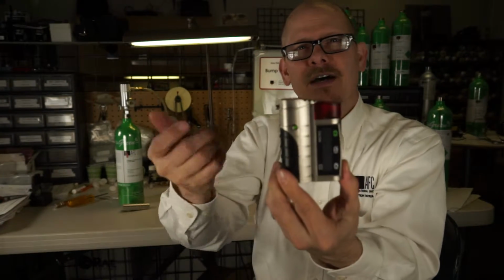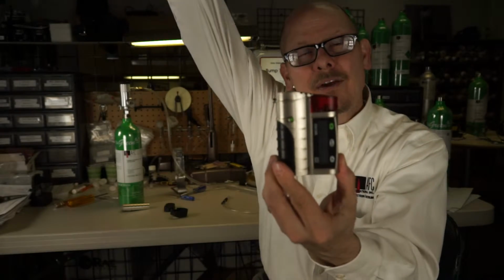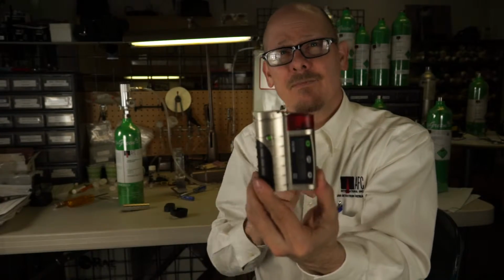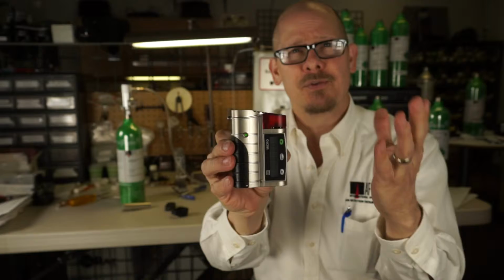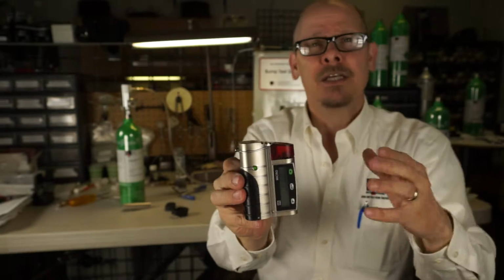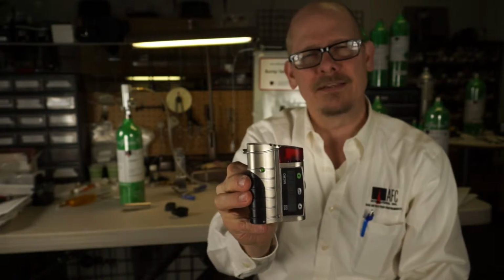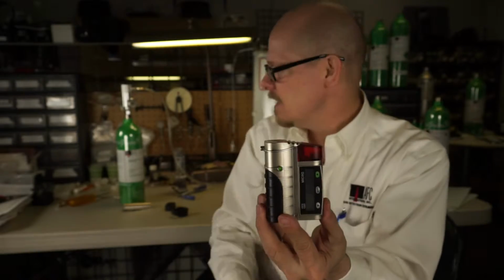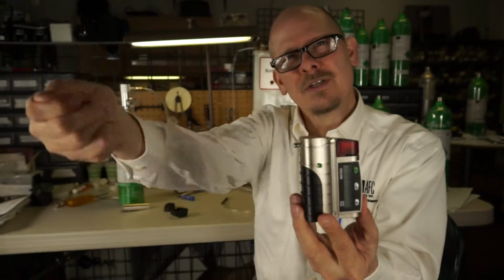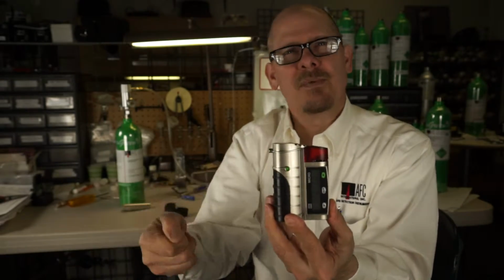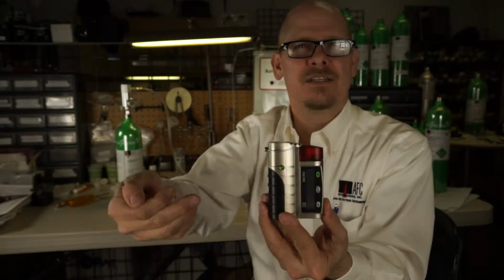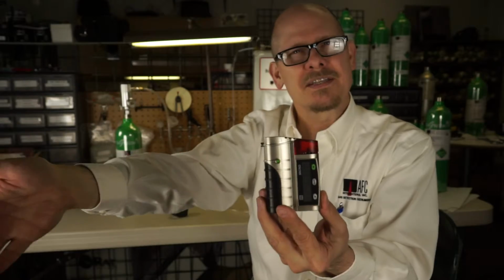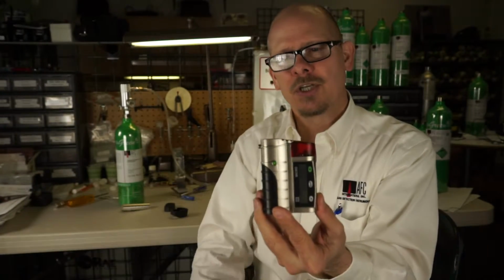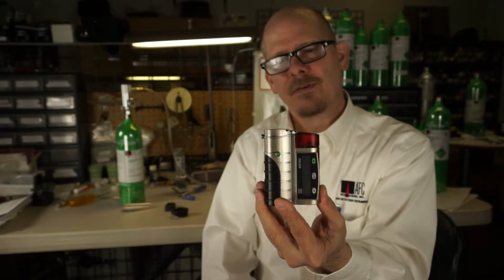I can add a probe or tubing to go up higher or extend my reach. Remember the rule of gas detection - you've got to be where the gas or vapor is to detect it. So using a smart pump like this is a very smart thing. I can also attach hose and probe to get into crevices, furnaces, incubators, process areas, and extend my reach. That pump is a very, very nice feature.